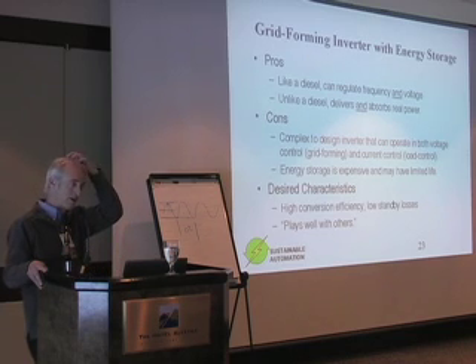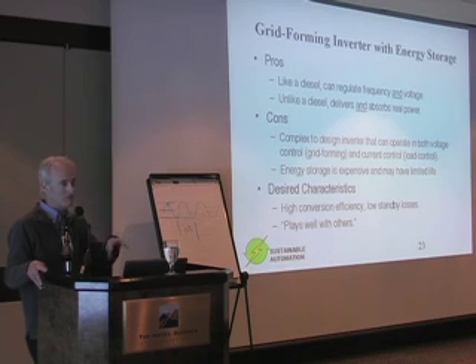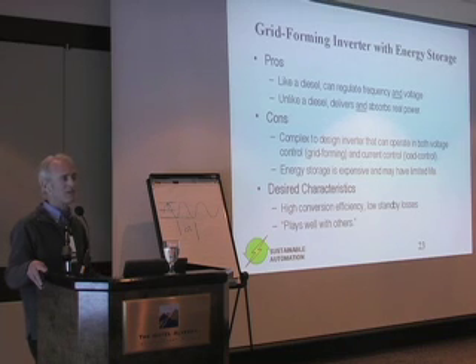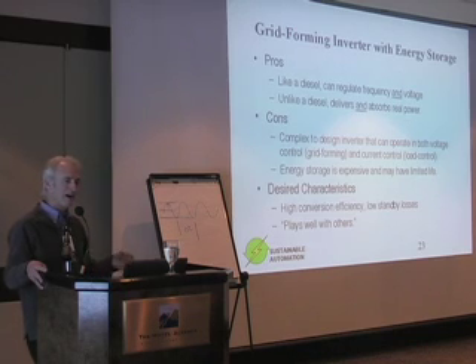You heard Russell from Power Corp talk about their flywheel product in terms of seconds of storage, which is very useful in providing time to start the diesel, but not that useful in preventing the need to start the diesel. So our target, and why we're currently using batteries for these systems, is that we want to be able to ride through relatively short-term wind energy deficits without having to start the diesel. I'm talking about wind lulls that may last from 1 to 10 minutes without having the spinning reserve online to handle that, or without having to panic and start a diesel just because the wind dropped off.